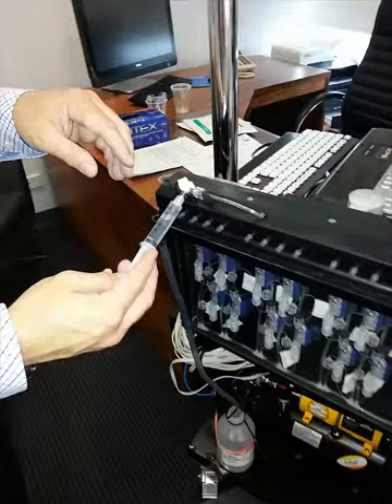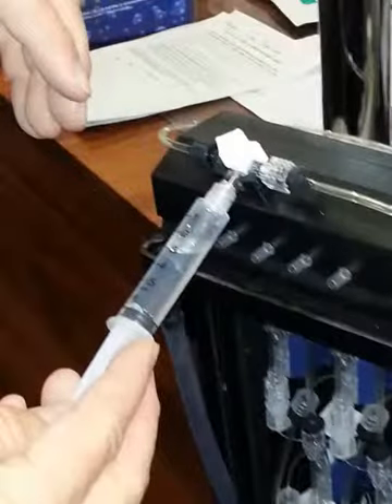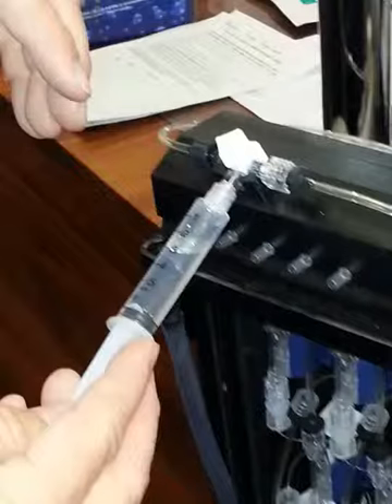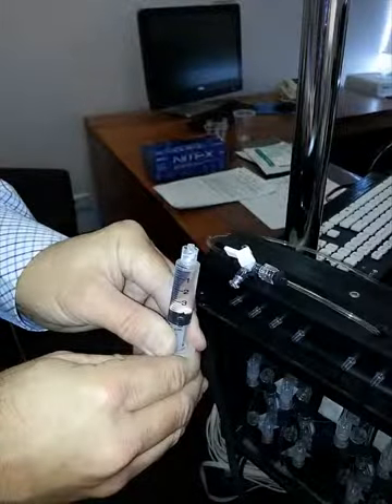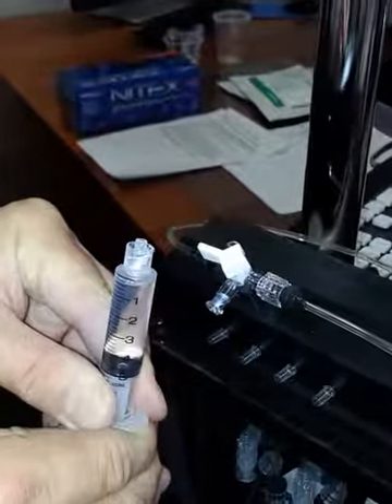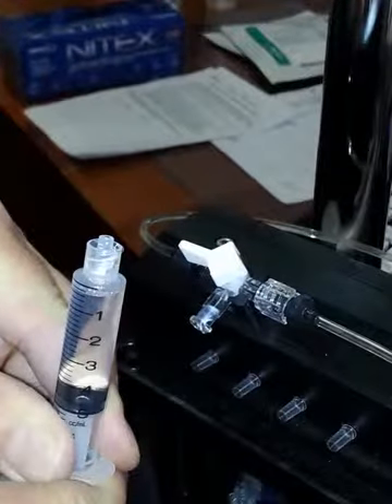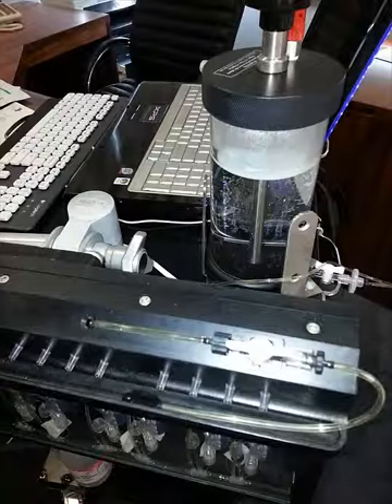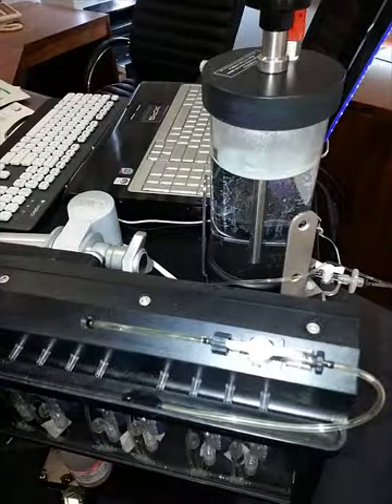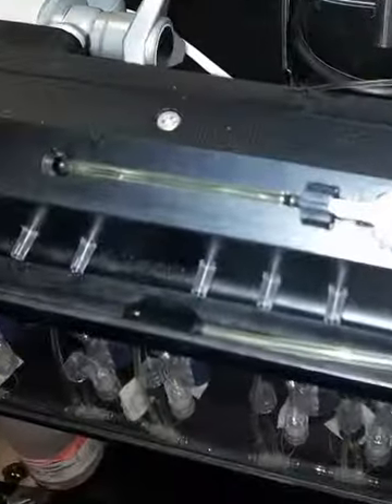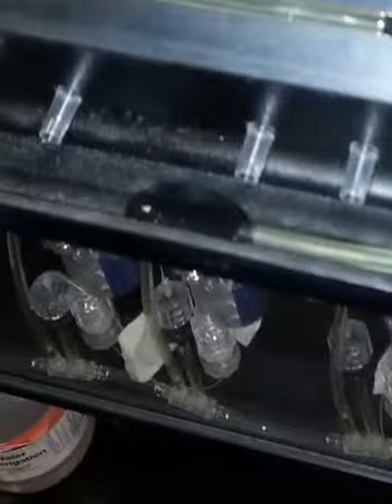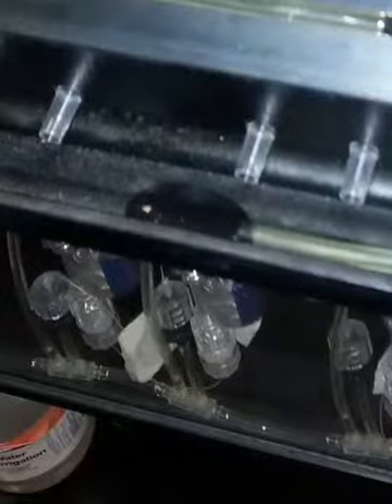Suctioning on the 5 ml syringe will now draw water from the reservoir into the syringe. There will of course also be some air which was in the tubing and the filter. Turn the tap to the left to close the inlet and expel the water from the syringe. Reattach the syringe and gently syringe water through the manifold until it comes out into the wastewater trough.